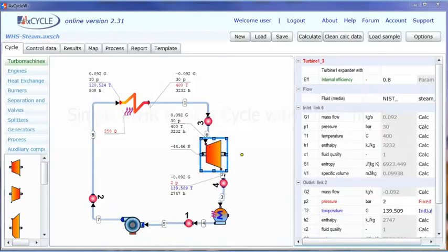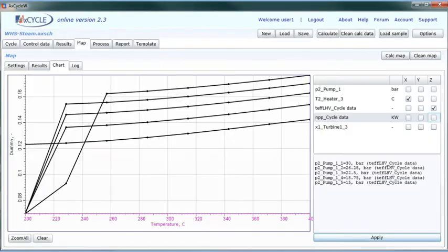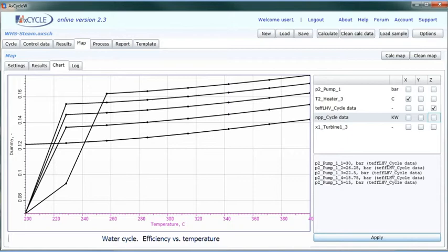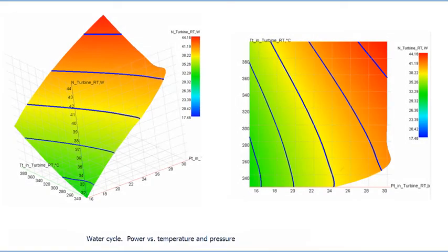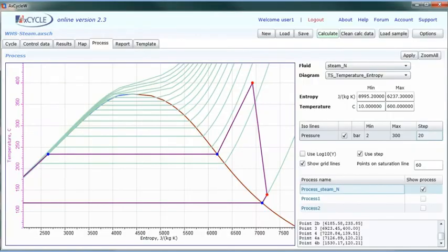The simple waste heat recovery Rankine cycle with water fluid is considered next. As the temperature of the heat sources is sufficient to vaporize water, such a cycle is worth studying. Here we are not limited by the fluid allowable temperature, and the maximum temperature can be taken. Calculation data are presented for an operation point of 30 bar, 400 Celsius. The water cycle power versus temperature plot and efficiency versus temperature plot are shown, along with contours of power versus temperature and pressure that define the operational range.